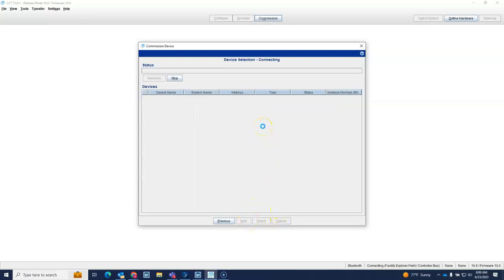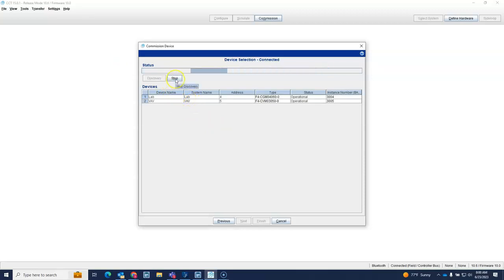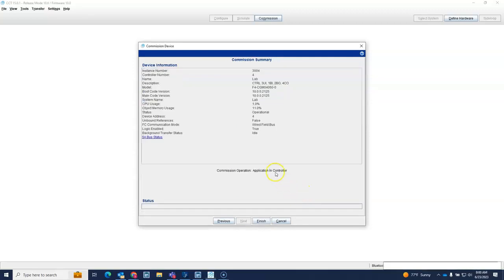And I can commission into controllers. Now the downside is anything other than 10.2, you're not going to be able to download to controllers, but you can at least commission into these guys. So here's the controllers on my trunk. I'm just commissioning into one of them just to show you that I could do it. Hit that, we're commissioning.